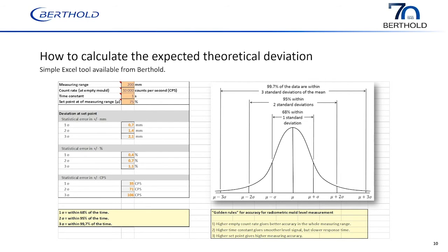I've been asked many times by customers, when do I need to change my source, Albert? And this question is not simple to answer because it actually depends. It depends on the customer and what they expect. I have seen casters using the same source for more than 20 years and casting with sources below 1000 CPS still working. But this is nothing I would recommend.